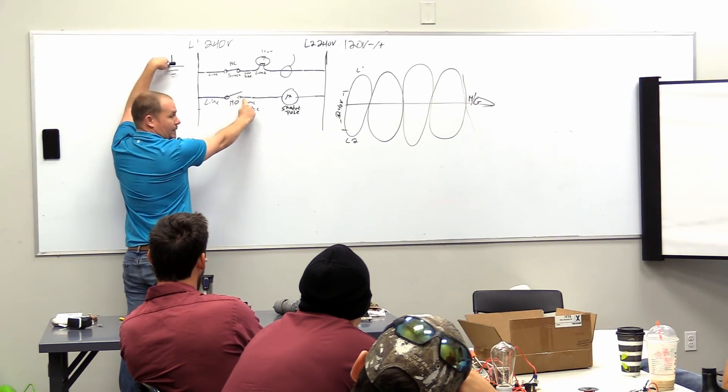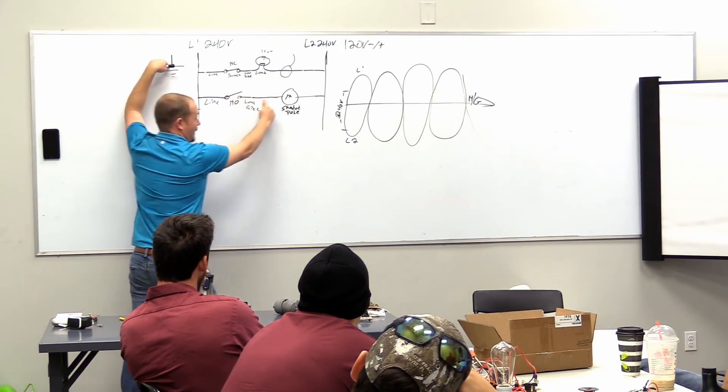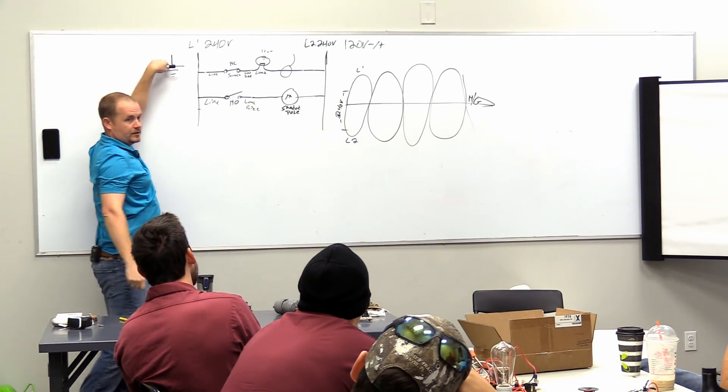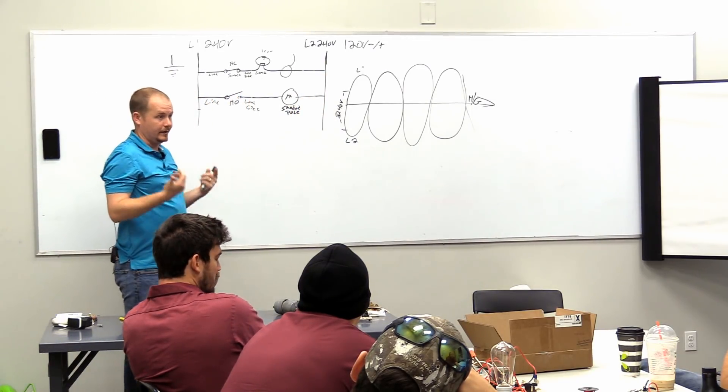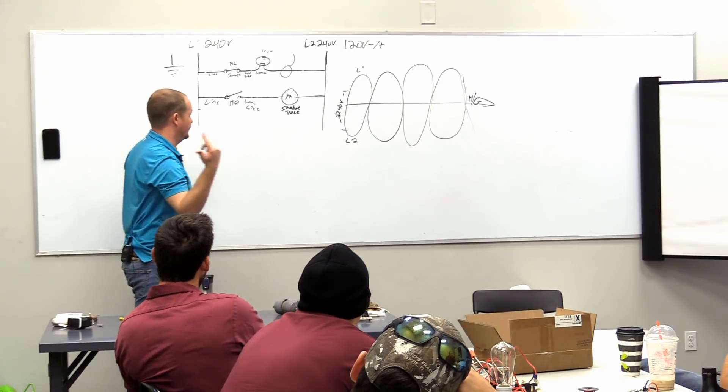Because the switch is open. Why am I reading 120? It's back feeding through L2, right. So I'm still reading 120 using ground. It really isn't telling me much. Now, let's do it this way.